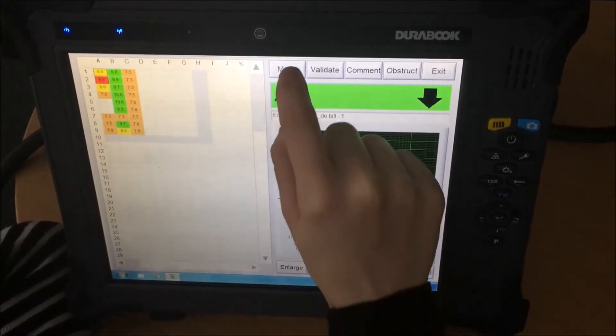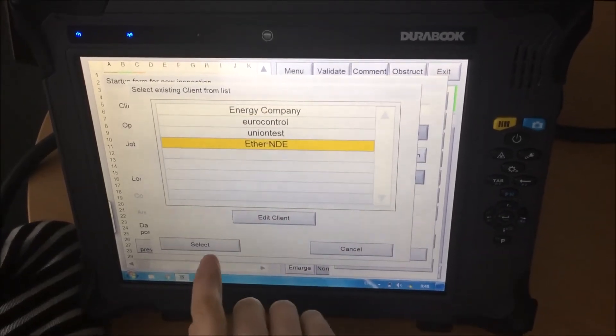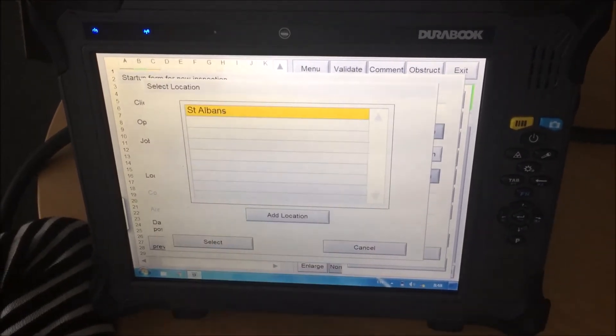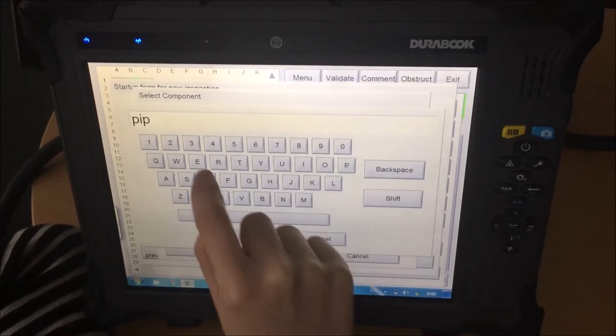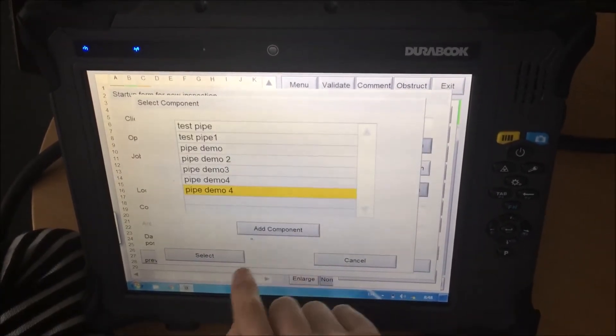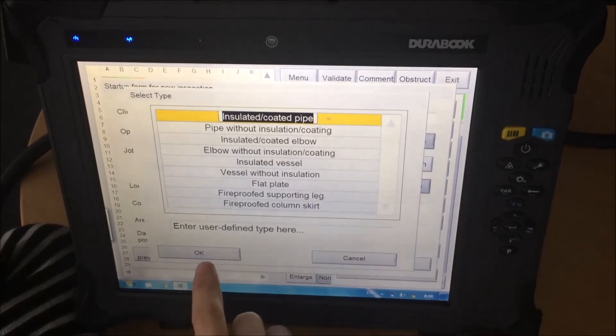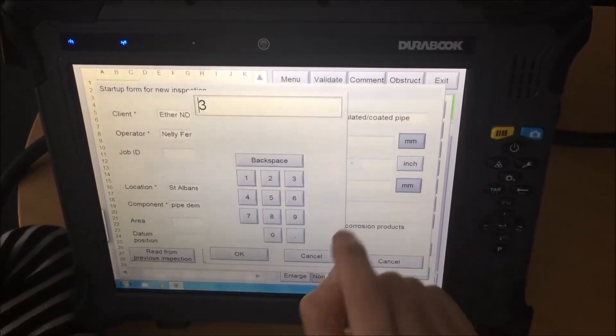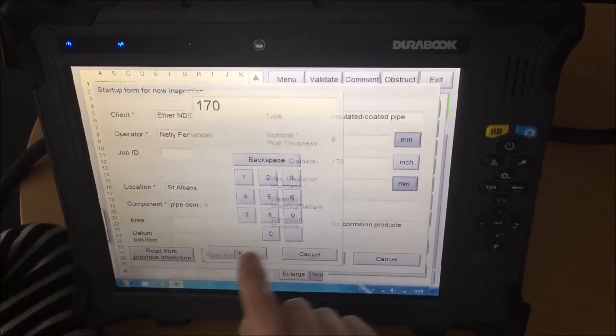To start an inspection, we need to click on Menu, then Start a New Inspection. We need to insert the client — in this case, Ether NDE — select the operator, mainly location St. Albans, select the component, we can add a new component, and select the type of component — in this case it is an insulated pipe. The nominal wall thickness is 8 millimeters and the outer diameter is 170 millimeters.